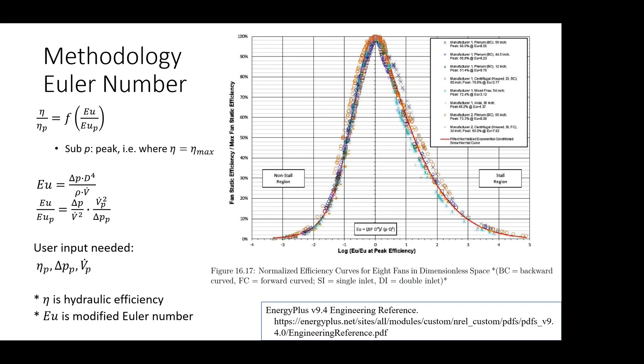This curve expresses the functional dependency between the ratio of fan efficiency and the ratio of Euler number. The y-axis is efficiency at any operating point over the peak efficiency, and the x-axis is the Euler number over the Euler number at the peak point — the point where the fan operates at maximum efficiency. Since we're only concerned with the ratio of Euler numbers, the user only needs to input one data point of efficiency, pressure, and flow rate. With that, we can estimate the efficiency at any operating point.